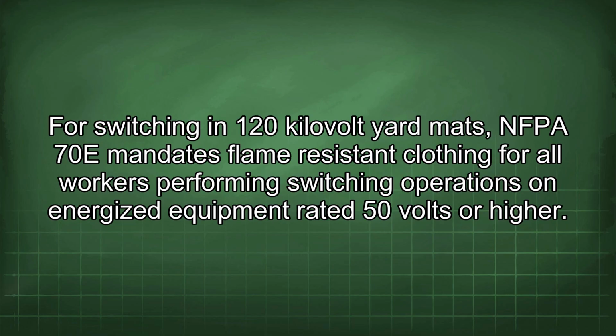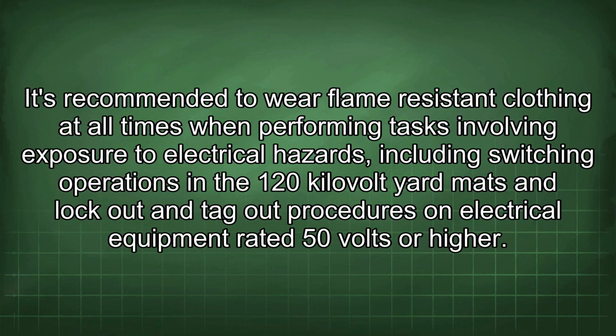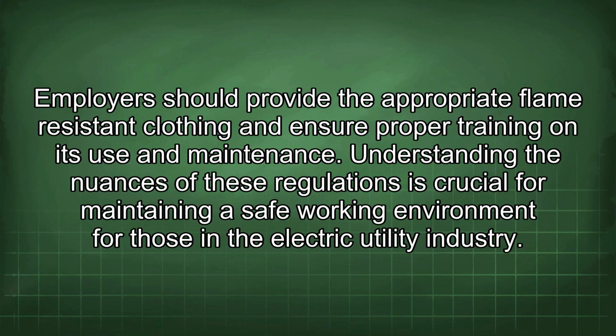For switching in 120 kV yard mats, NFPA 70E mandates flame-resistant clothing for all workers performing switching operations on energized equipment rated 50 volts or higher. It's recommended to wear flame-resistant clothing at all times when performing tasks involving exposure to electrical hazards, including switching operations in the 120 kV yard mats and lockout and tag-out procedures on electrical equipment rated 50 volts or higher. Employers should provide the appropriate flame-resistant clothing and ensure proper training on its use and maintenance.